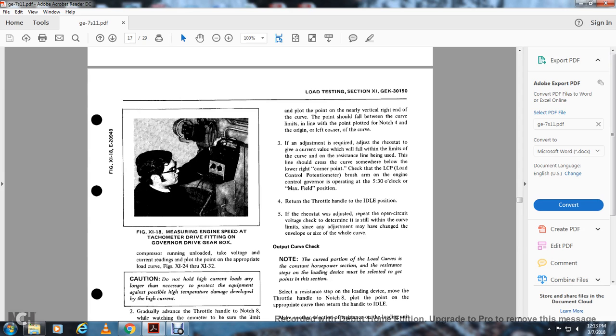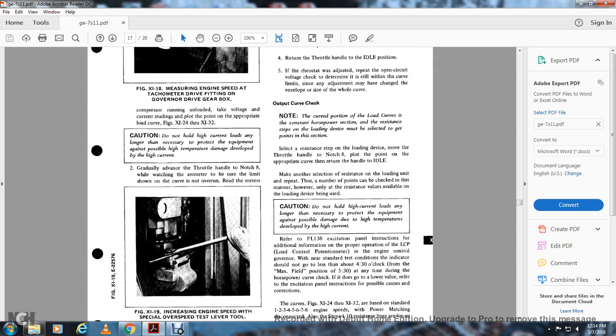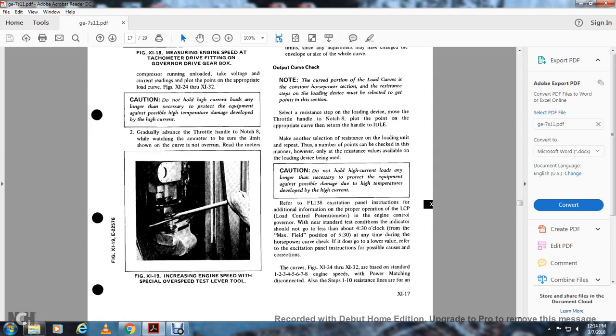Return the throttle handle to the idle position. If the rheostat was adjusted, repeat the open circuit voltage check. Determine that it is within the curve limits. Since any adjustments were made, change the envelope size for the whole curve, or repeat your output curve check. Note that for the curved portion of the load curve, the constant horsepower section, the resistance step of the loading device must be selected to get the points in that section.